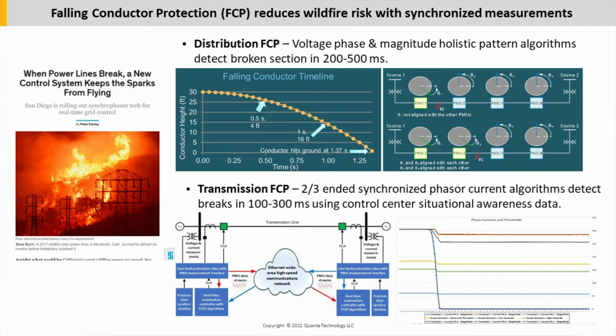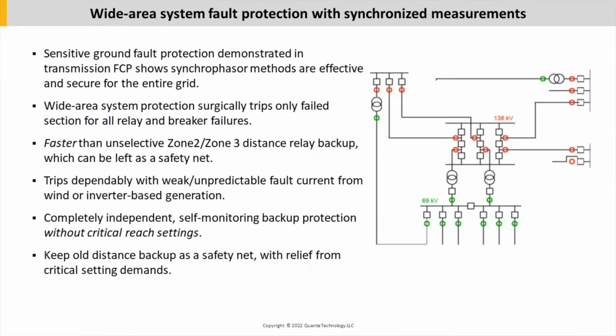We use the same falling conductor invention with new algorithms to monitor transmission lines and trip long before a broken conductor reaches the ground. Because tree contact with unbroken lines can also cause arcing faults and fire ignition, we included yet another innovation: ultra-sensitive ground fault detection with synchronized current data, which trips for faults of up to 5,000 ohms.